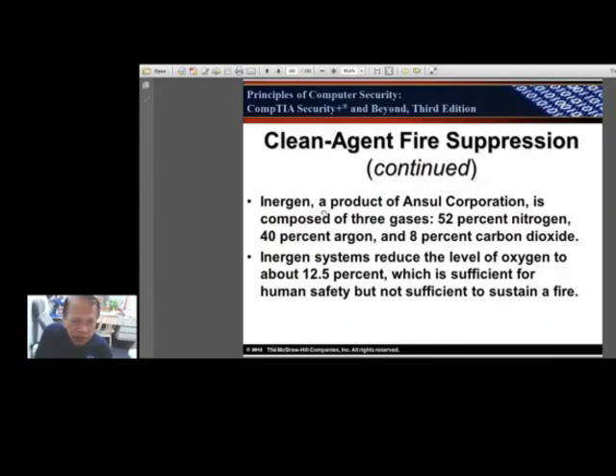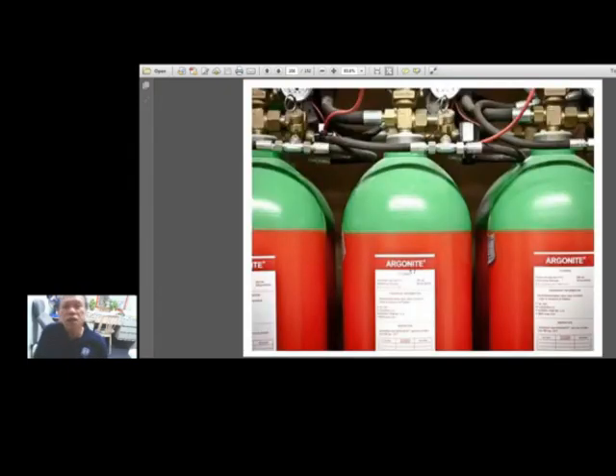Clean agent fire suppression. Inergen is a third one. Inergen is a product of Ansul Corporation. It is composed of 3 gases: 52% nitrogen, 40% argon, 8% carbon dioxide. Inergen systems reduce the level of oxygen to about 12.5%, which is sufficient for human safety, but not sufficient to sustain fire. So that's how this Inergen works. No? And here is a picture of that argon gas or argonite gas, which is also an inert gas.